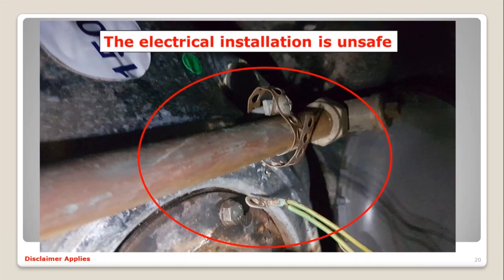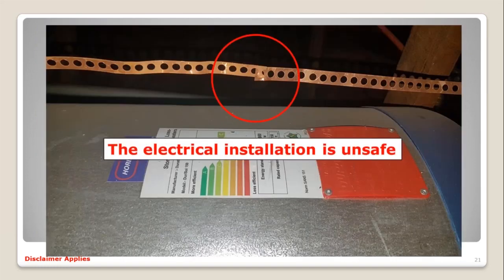Yes, the fact is that the earth resistance from the geyser to your distribution board, because that's where the main earthing is, is that there's no low resistance path. So if there is a leakage current, it will need to go the longer, further route to detect its tripping function or earth leakage function. So if it's not connected, the circuit breaker and the earth leakage can't see the leakage through the earthing of the system. That's why it's important to always make sure that you earth your flange and the bonding of your hot and cold water pipes.